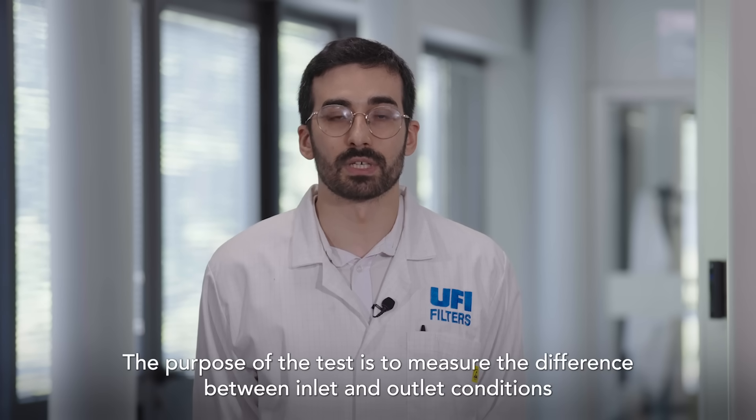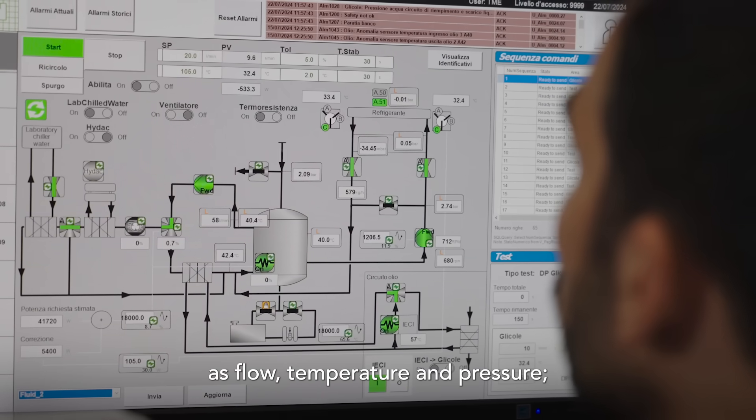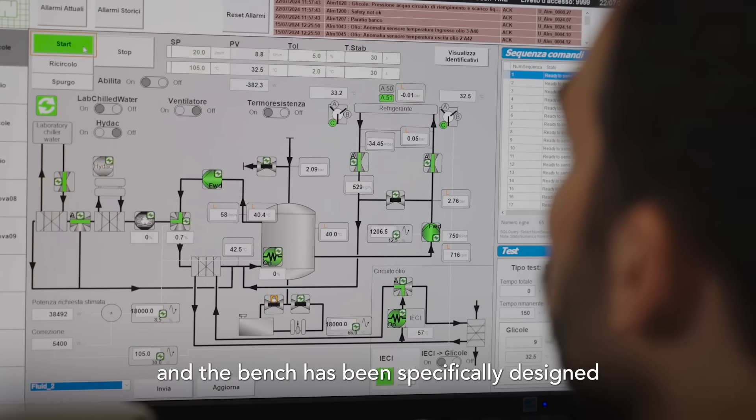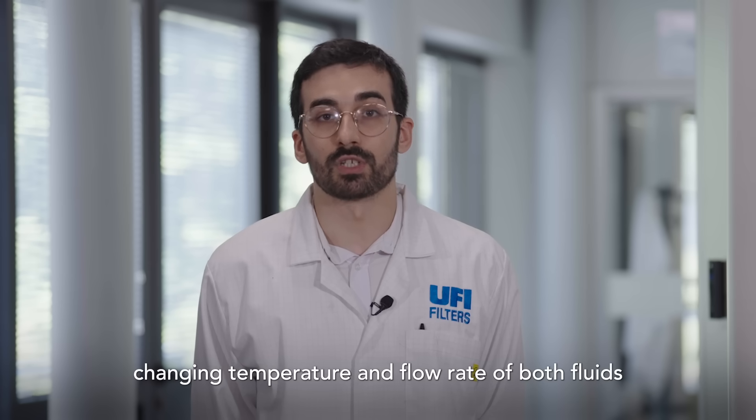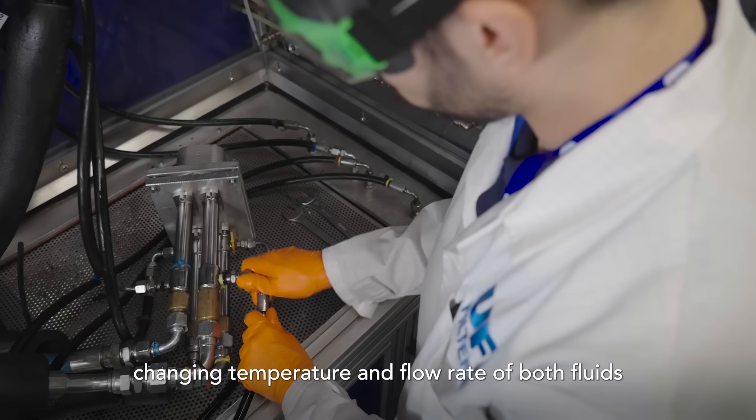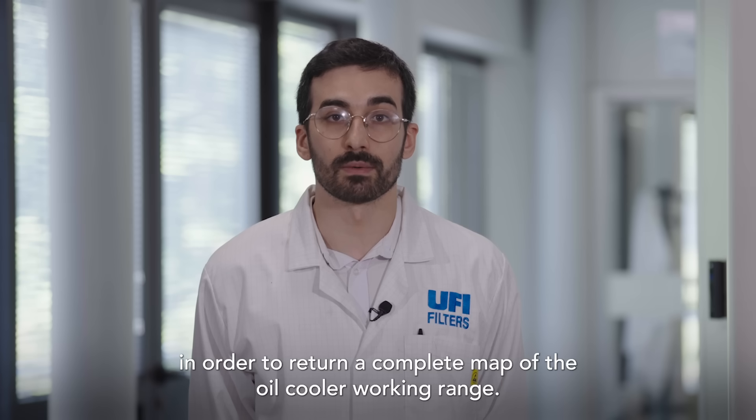The purpose of the test is to measure the difference between inlet and outlet conditions like flow, temperature, and pressure. The bench has been specifically designed to test a wide range of conditions, changing temperature and flow rates of both fluids in order to return a complete map of the oil cooler working range.